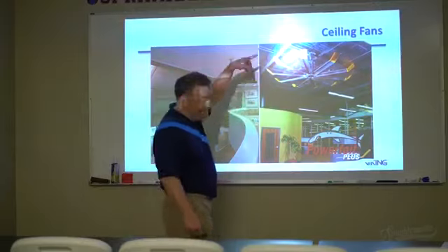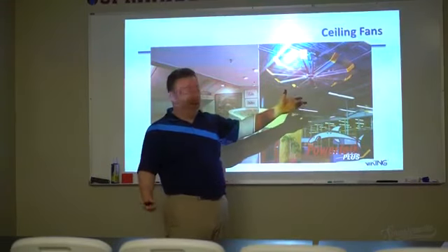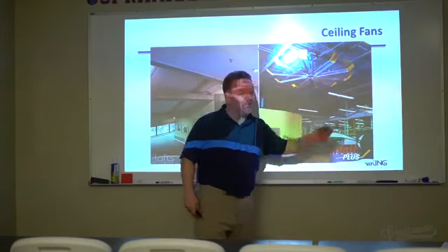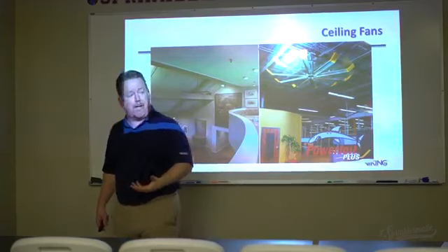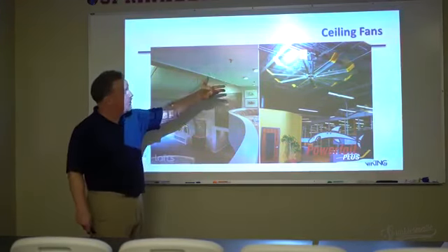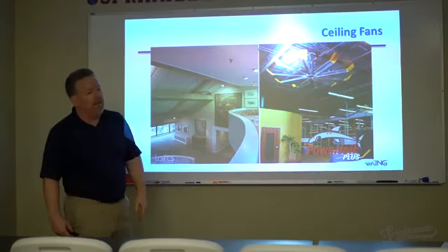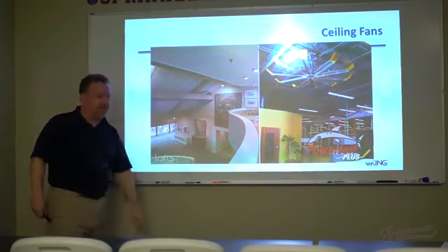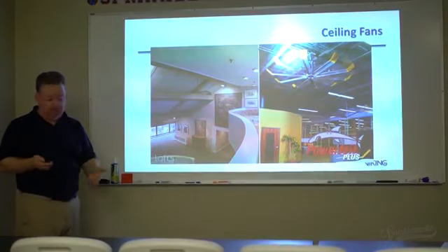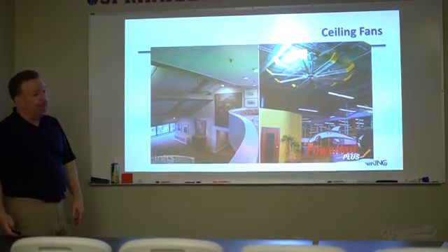The problem is, what does this thing do when it comes to my sprinklers? I don't know. We didn't know at the time. What we thought was that it could be an obstruction to the spray pattern, especially for ESFR sprinklers. What we found out is that, no, not so much. They didn't have the impact that we thought they were going to have on either ESFRs or the standard spray sprinklers. That's surprising. Yeah, it was a bit surprising.